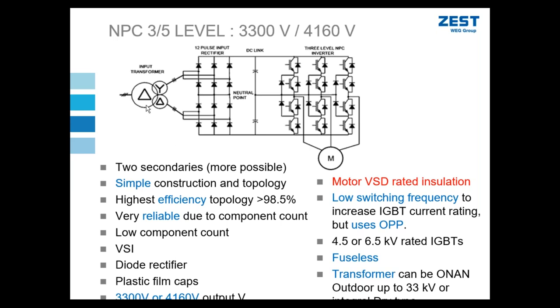So this topology should be known to most. We use in general an input phase shift transformer, the simplest form being a 12 pulse, 2 secondaries. We can increase this to multiple secondaries. We need to then also increase the number of input rectifiers. And this supplies our DC link, which we split by introducing a neutral point. So the topology here looks very similar to a low voltage topology, except we introduce this neutral point and we're able to clamp this neutral point using the 2 inside IGBTs, which we'll discuss in a little bit more detail shortly.